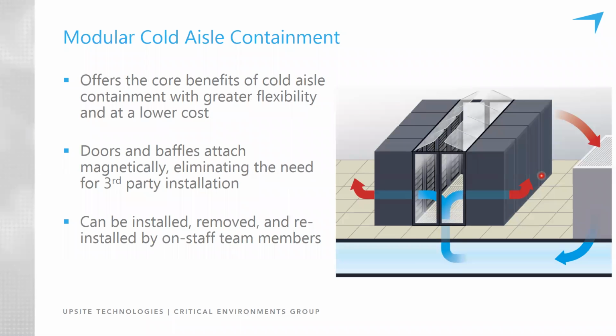And when we look at modular or partial cold aisle containment, I mentioned that there's that gap between the baffles in the top of the aisle. And this gap does not affect the potential for optimizing that balance between supply and demand air. And I'll point that out more clearly in the section that we talk about of bypass airflow. The benefits of modular partial containment is that it can be attached by staff, it can be relocated by staff, it doesn't require third-party installation or construction activities.